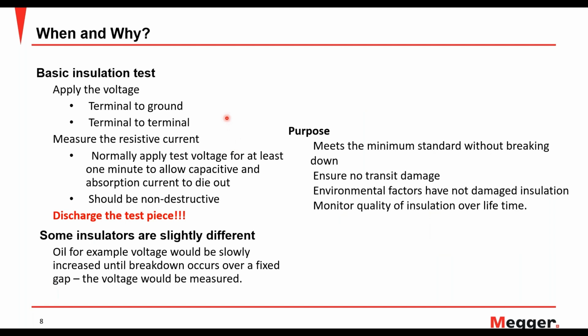So what is the basic insulation test? When do we do it and why do we do it? In a basic insulation test, you apply a voltage, terminal to ground or terminal to terminal, depending on your aim behind performing the insulation test, and measure the resistive current or leakage current. Normally, you apply the test voltage for at least 1 minute to allow the capacitive and absorption components to die out, and what you then get is mostly your leakage current, and that's what you want to measure. Based on that it will give out a resistance reading. So that's why it's important to wait a minute before actually taking the reading.